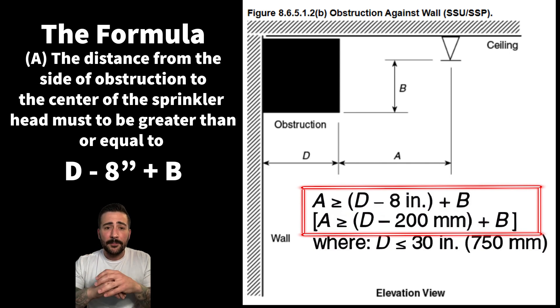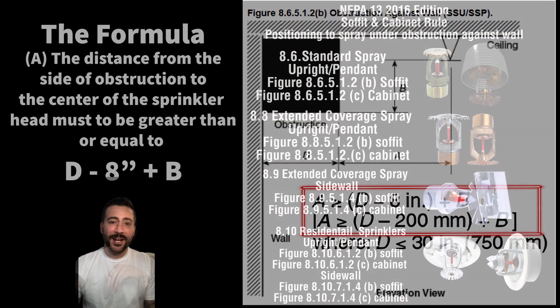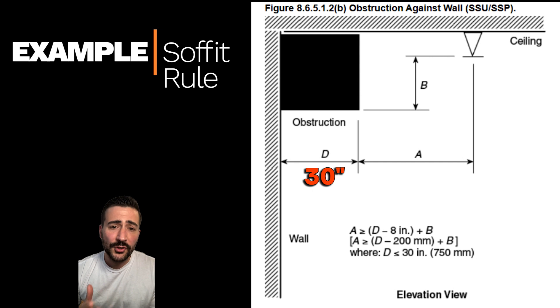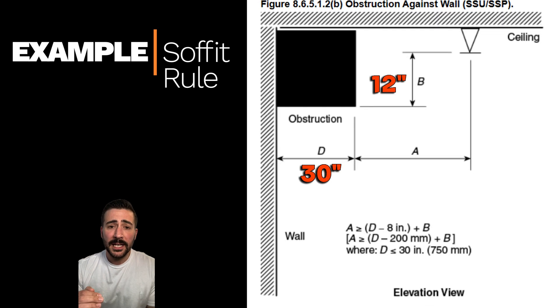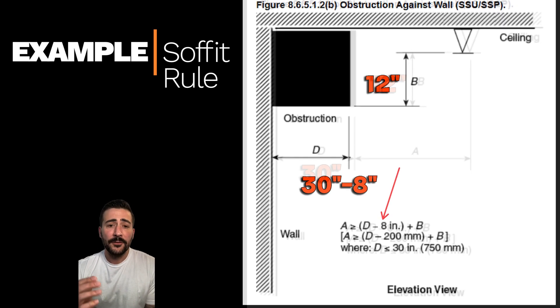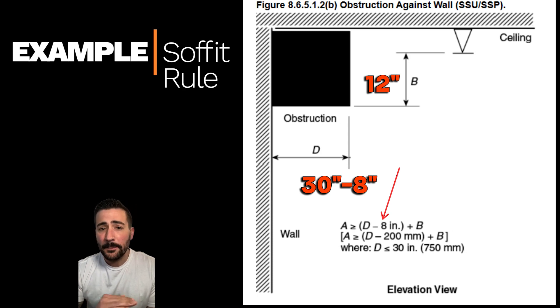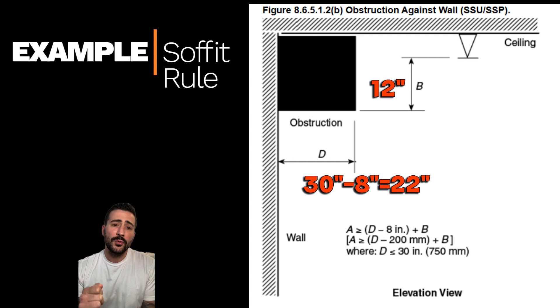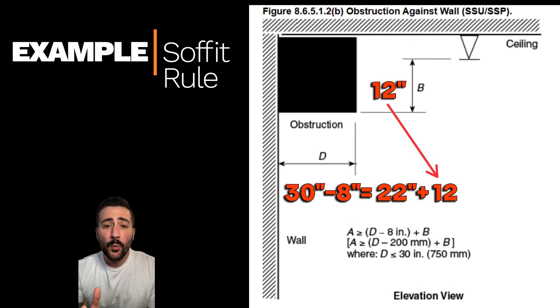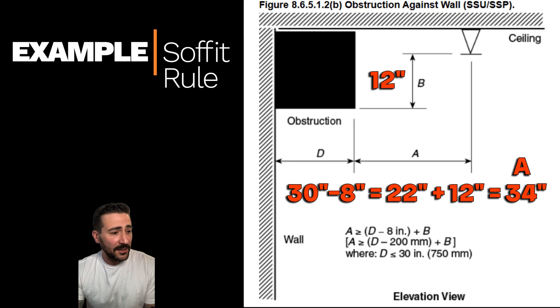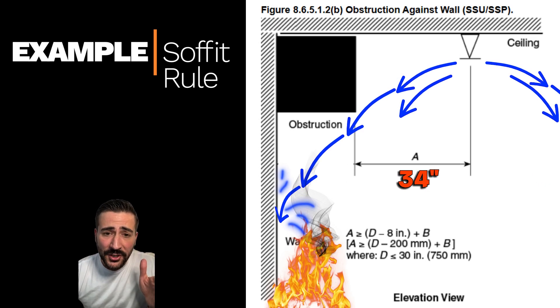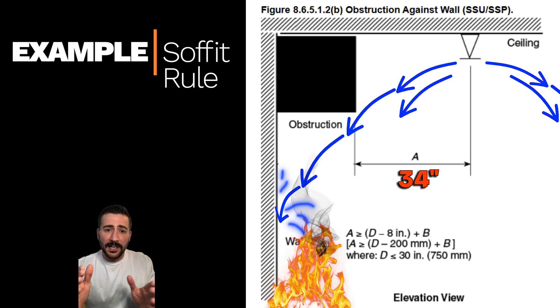This is always the same for all the available heads that we can use. Here's an example with realistic field numbers: D is 30 inches — the width of the obstruction — and B, the distance from the bottom of the obstruction to the sprinkler deflector, is 12 inches. First, take D (30 inches) and minus eight — always — giving us 22 inches. Then add 12 inches to the 22, giving us 34 inches. That is how far from the side of the obstruction to the center of the sprinkler head we have to be to achieve a full spray pattern underneath our obstruction.